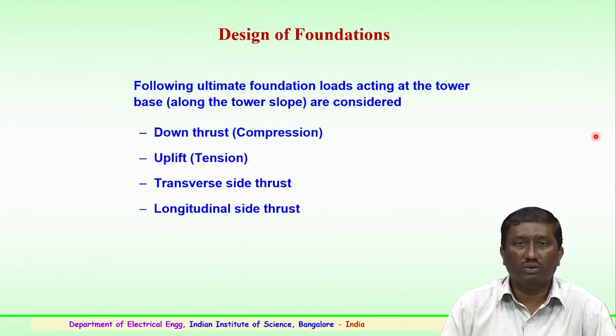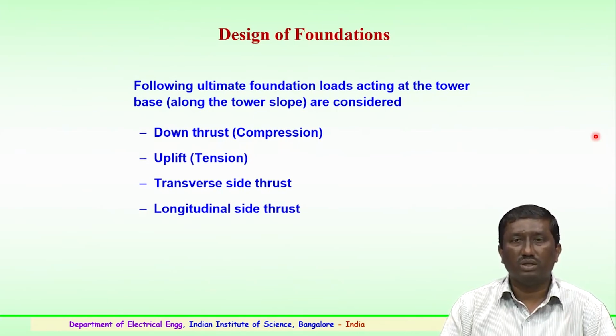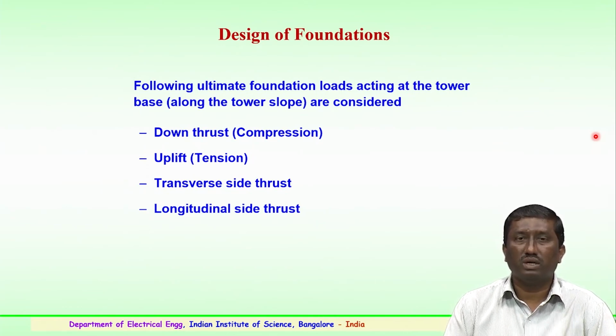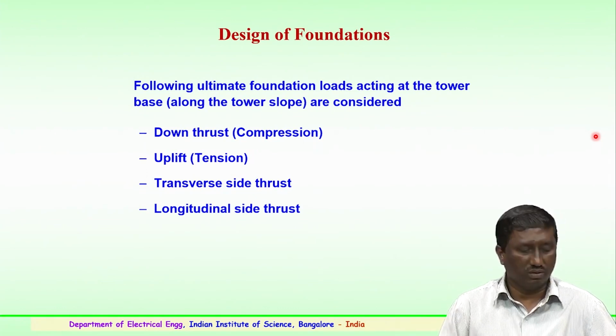For the design of foundations, again considering various aspects, the following ultimate foundation loads which act on the tower at the tower base along the tower slope are considered: the compression load, which is a downward thrust the tower sees; the uplift, which is a tension loading that comes to the tower; the transverse or side thrust; and then the longitudinal thrust. Several of these aspects have to be considered, apart from other dynamic changes which the tower sees. All of this is to be considered for the design of a suitable foundation, which is very important for the tower.